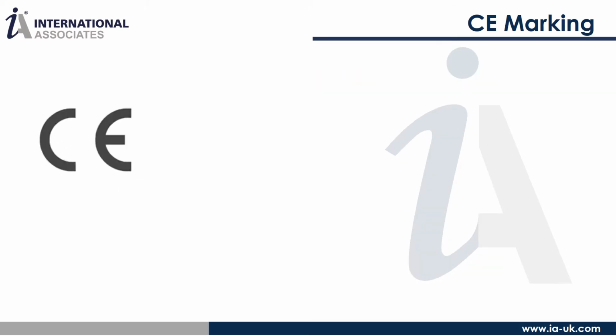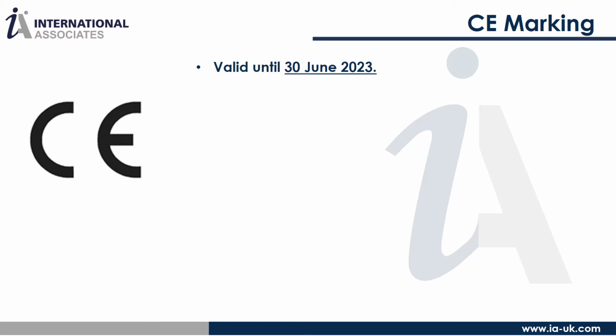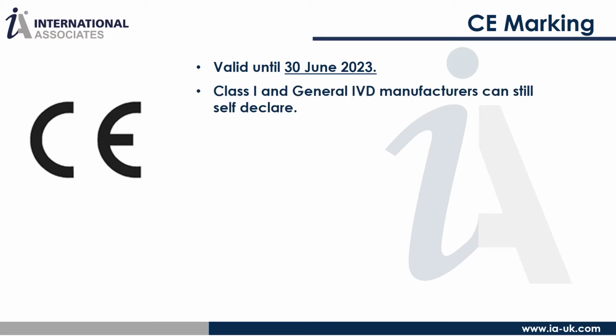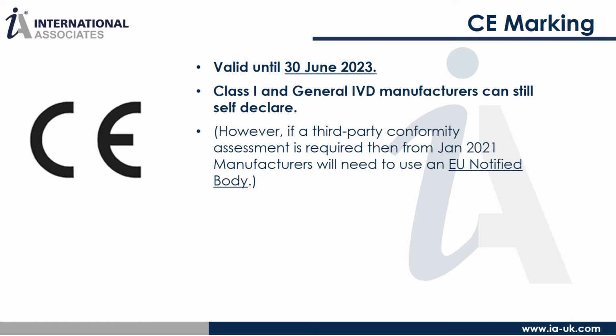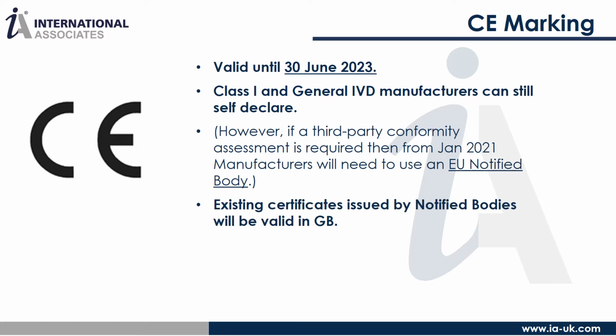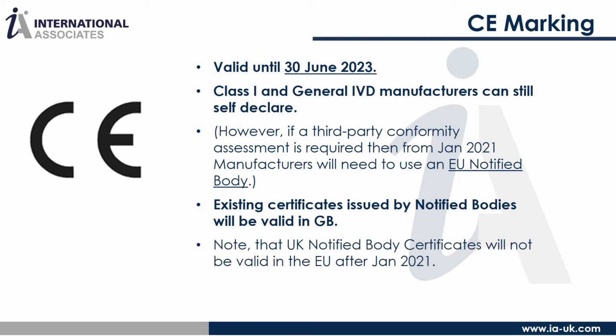So where does that leave the CE mark? The CE mark will be valid until the 30th of June 2023 to allow manufacturers to transition. Class 1 and general IVD manufacturers can still self-declare and place on the market. However, if a third-party conformity assessment is required, i.e. for higher classes, then an EU notified body will be required. Hence, if you are a UK-based manufacturer using a UK notified body, then this will not meet the requirements. Existing certificates issued by UK or EU notified bodies prior to January 2021 will be valid in Great Britain. Note that UK notified certificates will not be valid in the EU after January 2021.